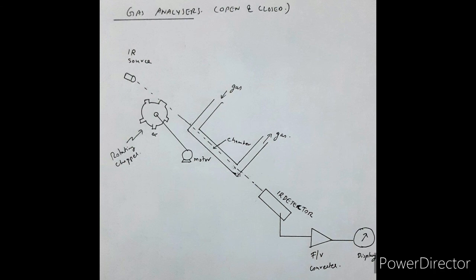While passing through, it is subjected to flashing with the help of a rotating chopper, which converts the IR beam into a beam of pulses. This essentially introduces a carrier into the system, which is detected using an IR detector located at the other end.